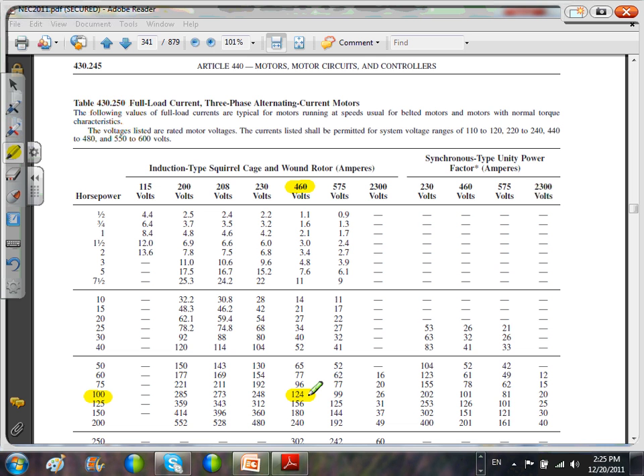And if you can see, guys, they give you the voltages here slightly less than the nominal voltage. Manufacturers rate the equipment slightly less than the nominal voltage, in this case taking into consideration voltage drop. So 460, when you start with 480 at the substation, you go all the way 100 feet, you're going to lose some voltage here. So this motor that's rated for 460 can run efficiently at 124 amps as long as you give it 460 or higher, or around 460.